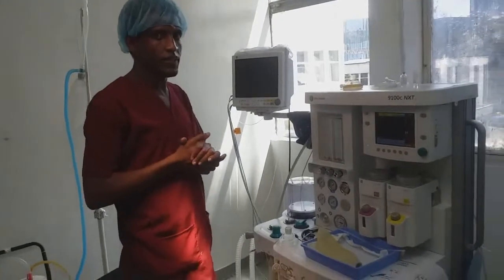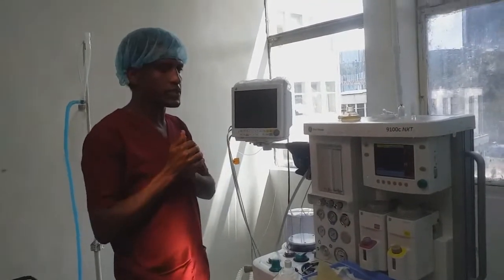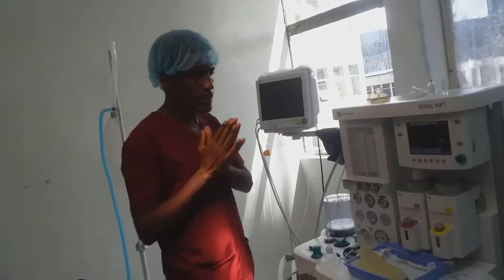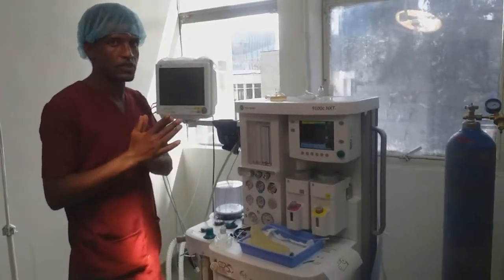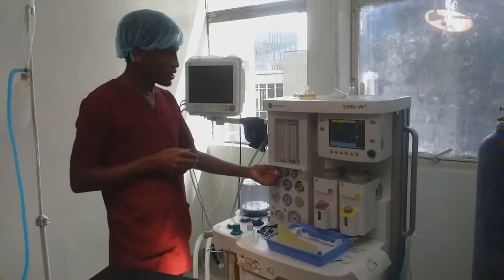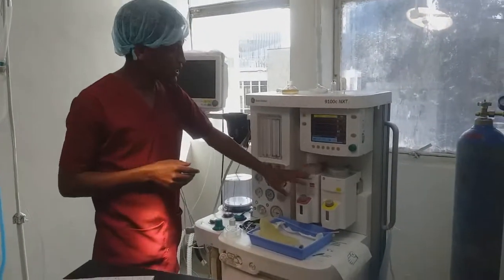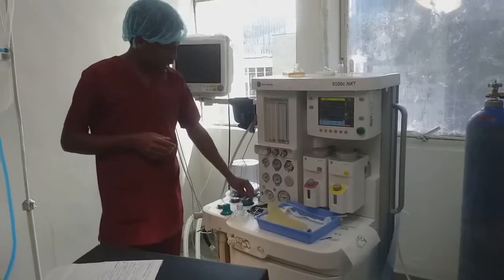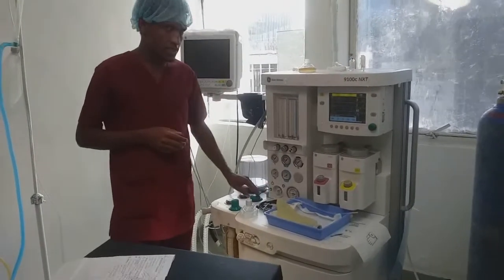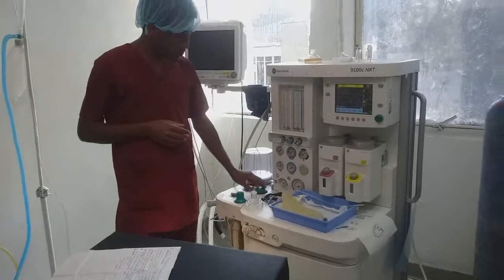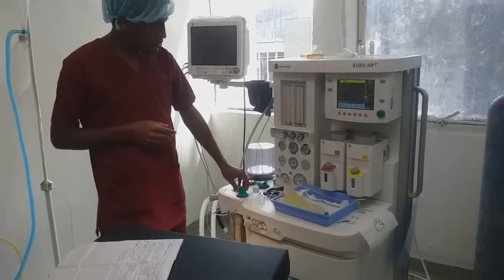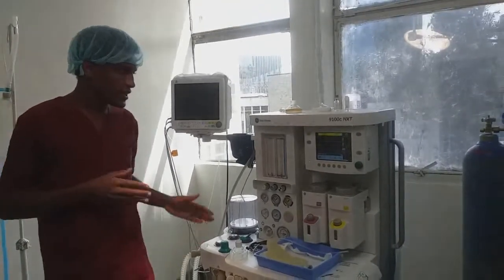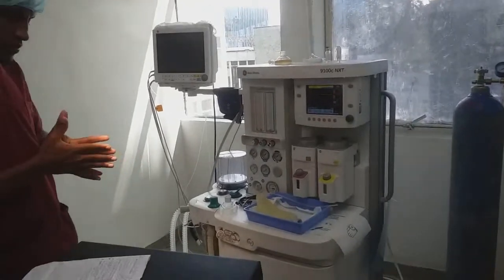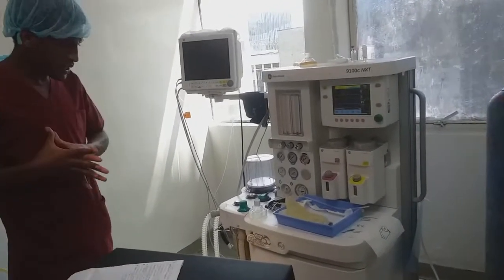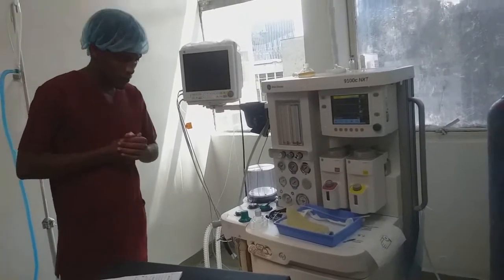After we did all the anesthesia machine checks, there is what we call the final position. Until the first patient arrives at the OR, the final position of the anesthesia machine should be: oxygen flow meter in the off position, vaporizer in the off position. Here there is the off position. The mechanical bag vent selector should be to the bag vent mode. The APL should be fully open, just like this. This is the final position of the anesthesia machine. Check out procedure at the end of anesthesia machine check.